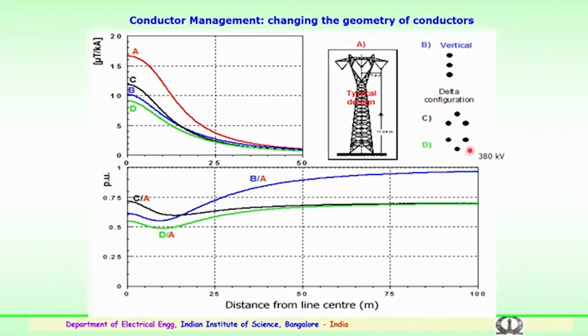The placement of the conductors is being modified, and studies have been carried out to see the fields' behavior. You can see here for the magnetic fields, that is the micro Tesla per kilo amp. So, it depends on the current rating or the load which is being carried by these conductors. For various current ratings in terms of kilo amp, the micro Tesla, that is the magnetic field, is estimated, and you see particularly in this configuration the magnetic fields are higher, and going in for either vertical or a delta or an inverted equilateral triangle type of arrangement of the conductors could lead to better performance of the line, and also the magnetic fields getting reduced. So, this is how it is being shown here, and this gives the per unit versus the distance from the center of the values.